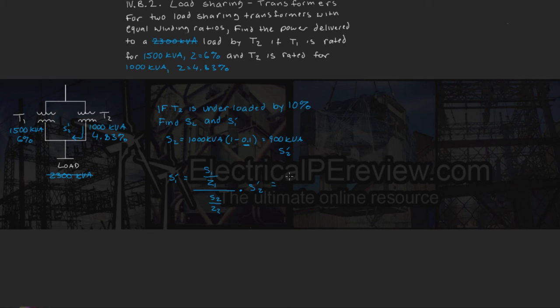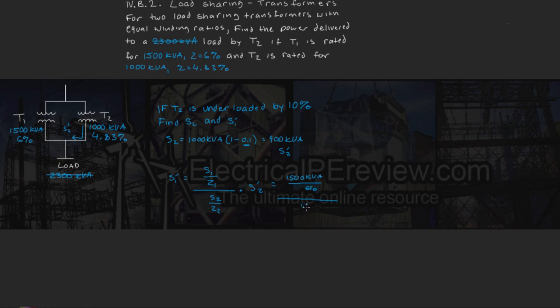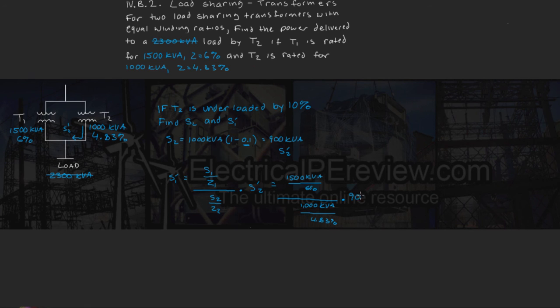So we plug in our values, we've got 1500 kVA divided by 6% over 1000 kVA divided by 4.83% times our underloaded amount, which is 900 kVA.